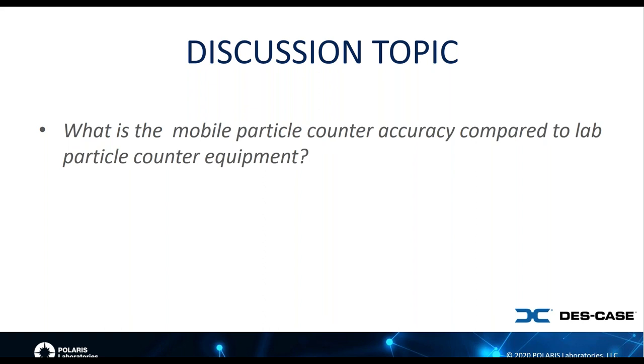Correct me if I'm wrong, guys, because I haven't seen a mobile particle counter recently, but as far as I understood, when they first came out, it was just going to give you a global number, and then there was a table that would convert to an approximate concentration of particles present. Yeah, so there are mobile particle counters on the market today that will report in the standard 4, 6, and 14 micron ranges that we report from a lab sample.